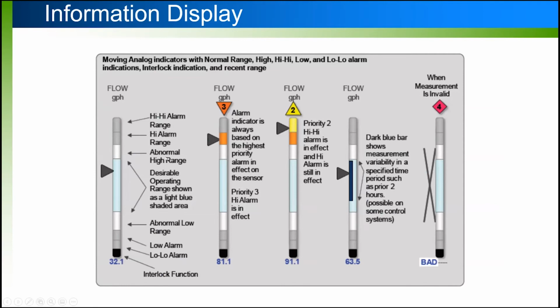If we scroll over to this fourth value, we see something else displayed. This darker blue area is sort of a trending alternative, showing where that process value has been within the last X number of hours, in this case 2 hours. So you can see where the process has been without necessarily taking up as much space as a full trend. If you have a lot of values to display but still want some trending feature, this is a great alternative.